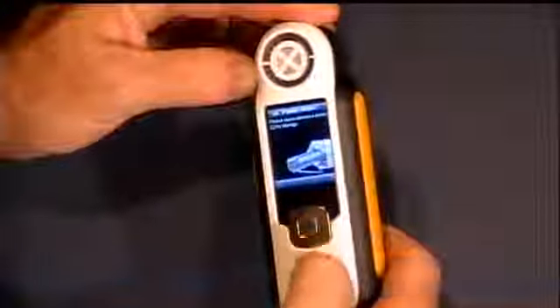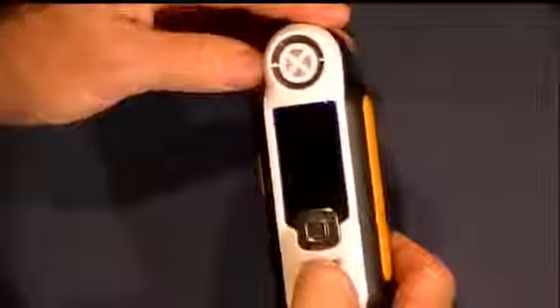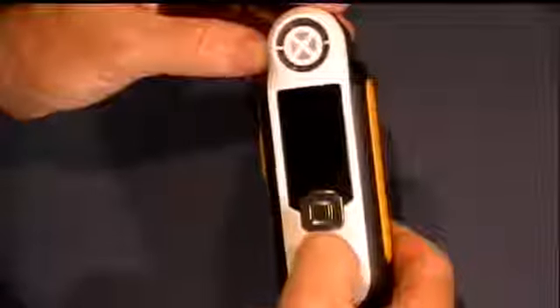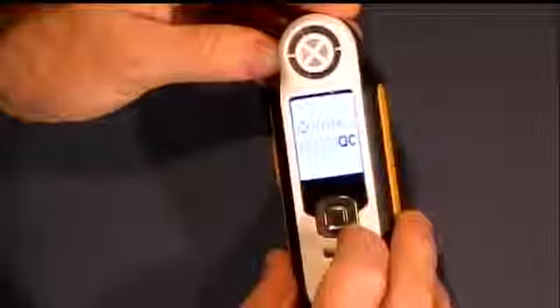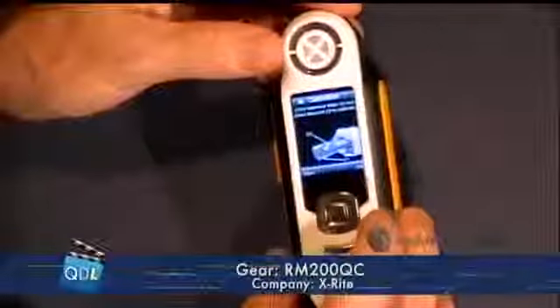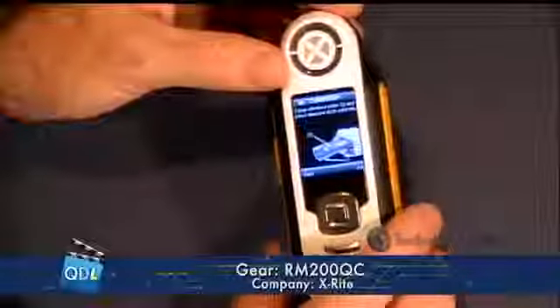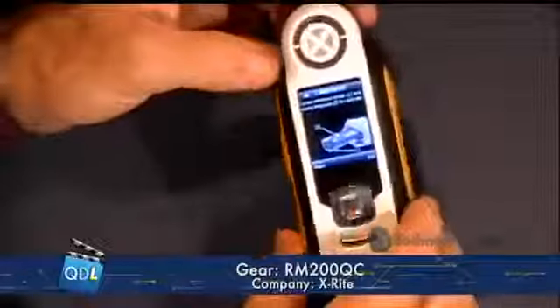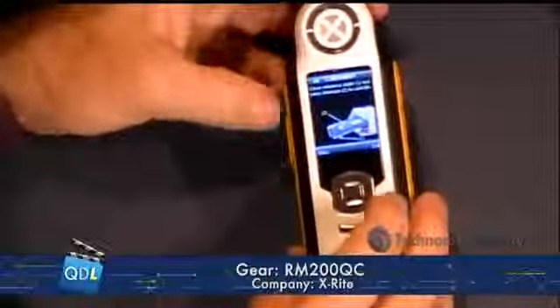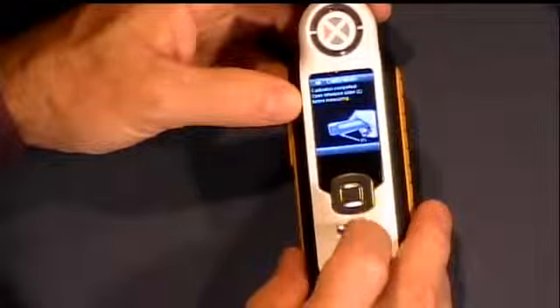One of the first things I want to do is shut the device off, so I can show you what happens when you power up. First thing that happens, I power up, and in a second it asks me to calibrate. It requires calibration every time you power it up. It reminds you that the lid needs to be closed, that's what this message says. I press my little trigger button, and it takes maybe 10 to 15 seconds to calibrate the device. Once it's calibrated, it's good to go, and we can start taking measurements.